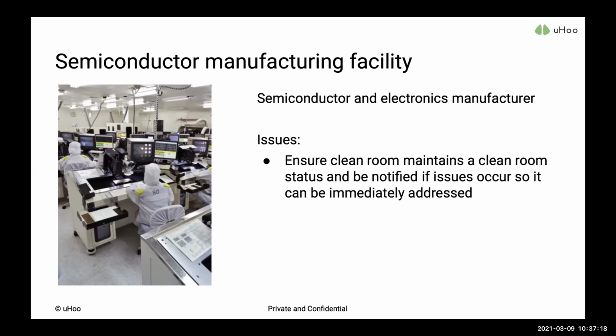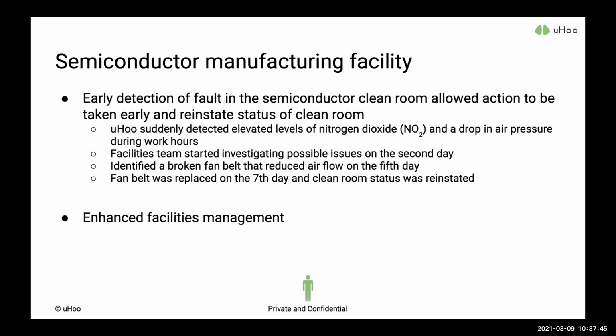But then there was one day when they saw a sudden increase in NO2 levels, which made them curious about what could be occurring inside the facility. They ran some tests trying to understand what was causing it based on the activities inside, and started investigating the HVAC system of the building. They found that one of the fan belts inside their HVAC was actually broken.